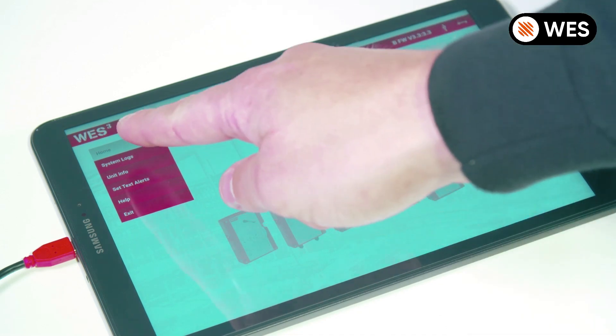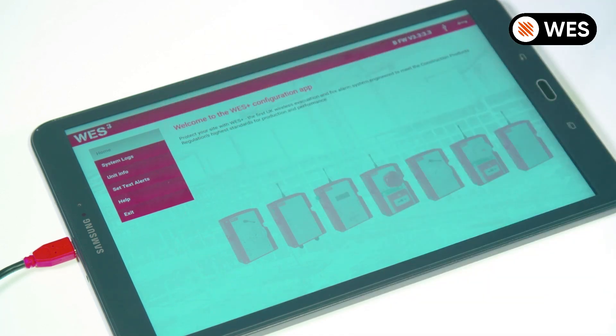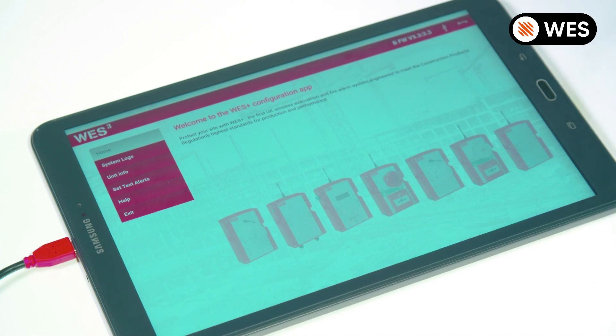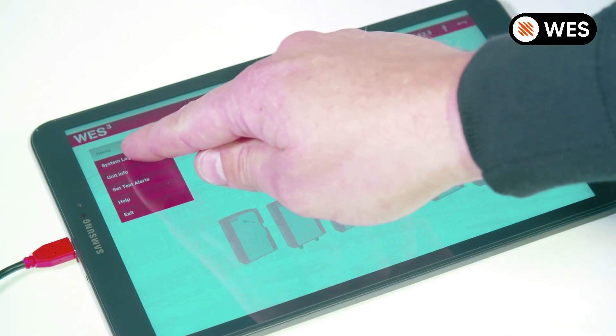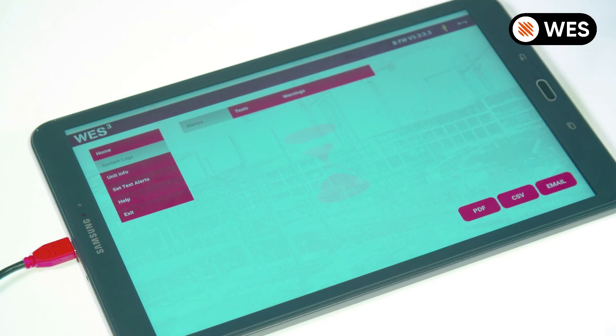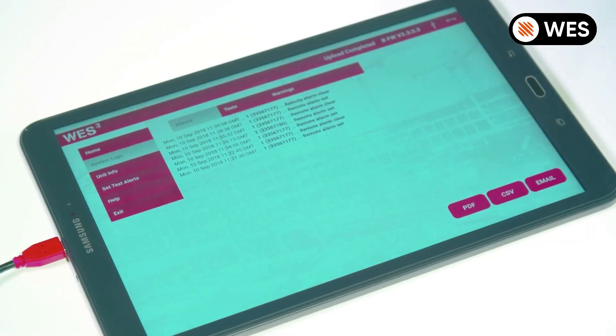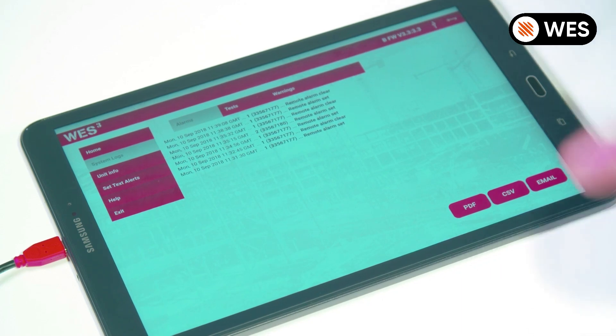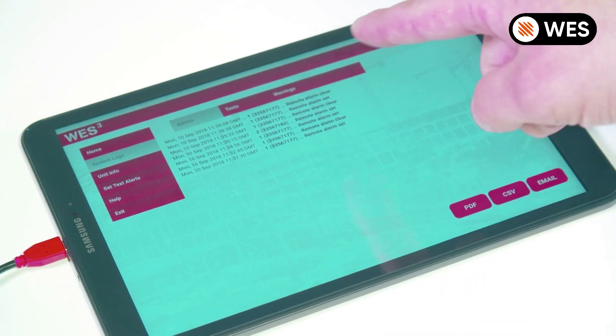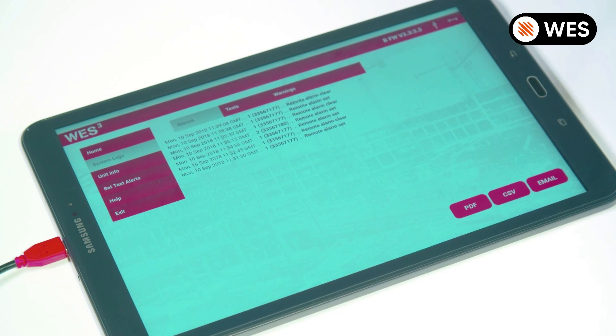As we can see in the top left, the app has automatically distinguished the difference between a WES 3 and a WES Plus unit. Now we can have a look through some of the options. Let's go to our system logs. It takes just a few seconds to load up the logs from this base station. Here we have a list of the alarms — we can also select tests and warnings. Everything that's saved on the base station is now on the app.